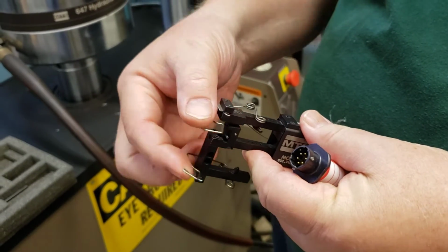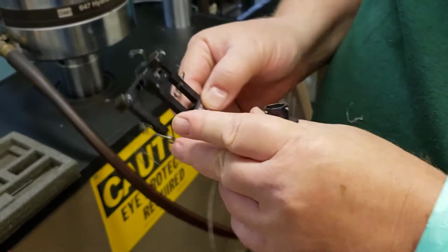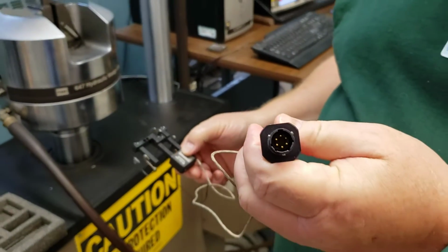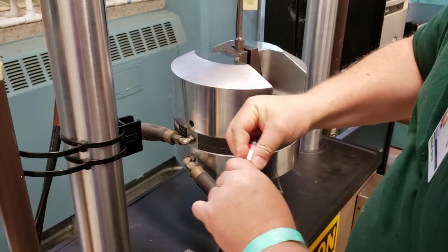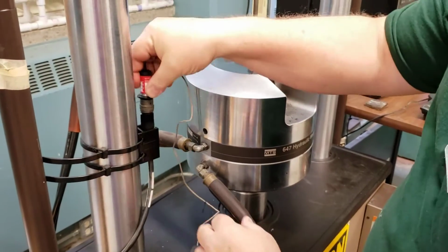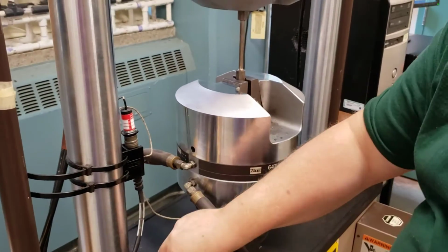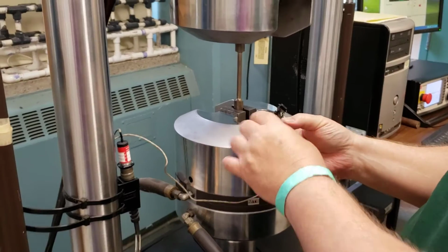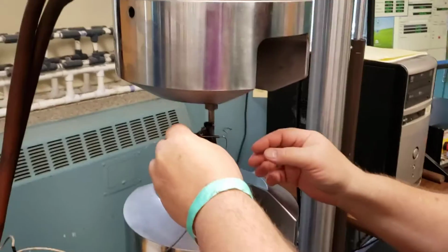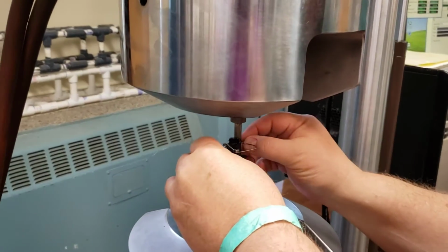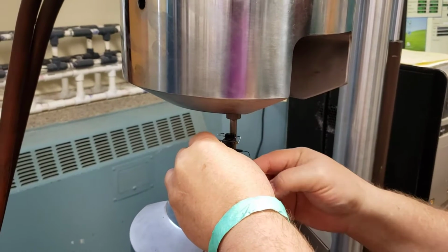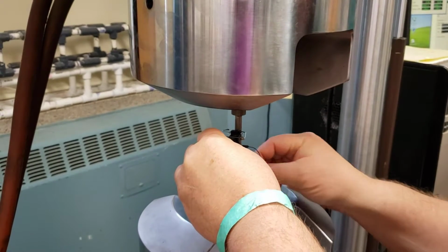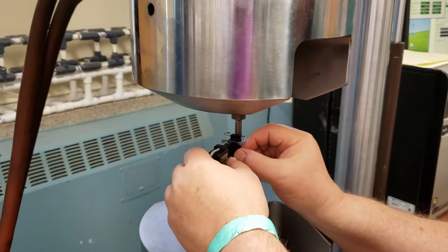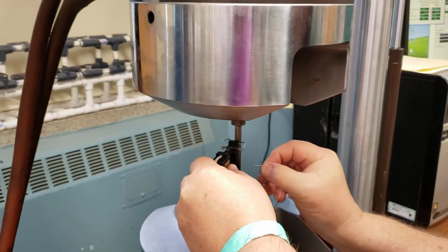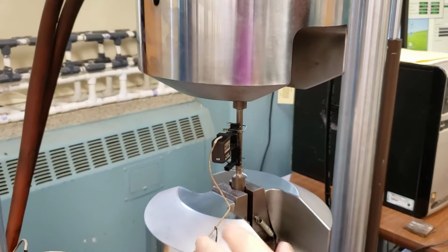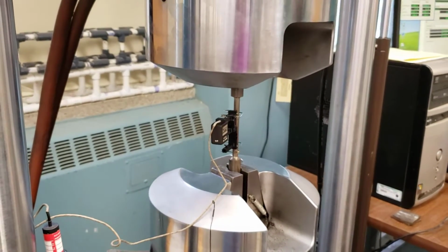It mounts on the sample with these two hookovers. The transducer plugs in very simply here. There we go. It's all lined up. It's in. And now this mounts by mounting on our specimen, bringing over our two hooks, and pulling the pin so it can go up and down and read.